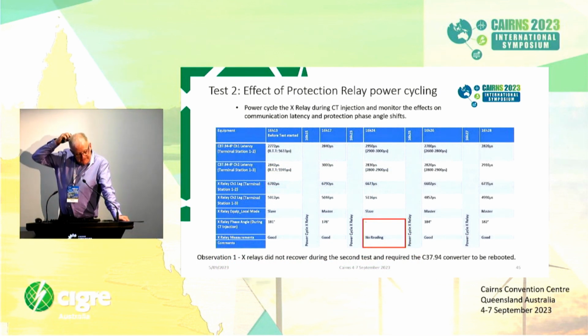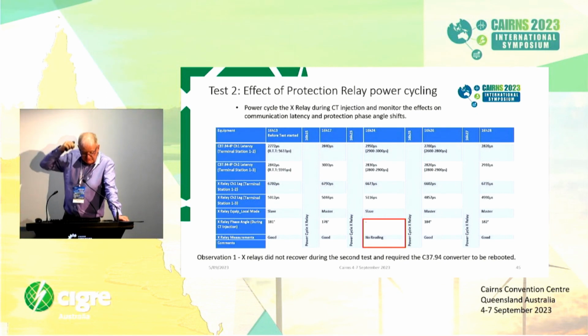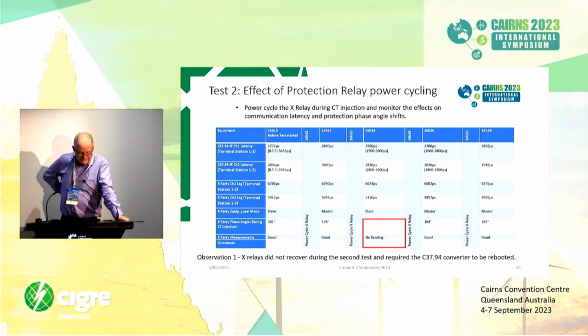The second test we ran was just the effect on protection relay power cycling. So we ran this test 4 times here. Once again, each test, with the exception of the one in the middle there, was successful. So with the first test, we power cycled the relay, all good. The relay then recalculates its round trip time when the comms comes back. That was all good, and it then uses that for the phase angle calculation in its protection algorithm.